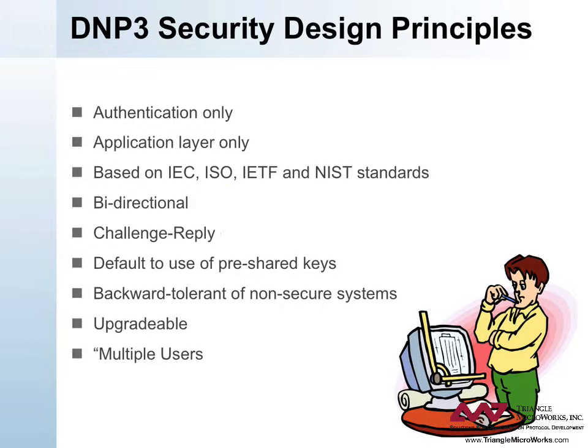DNP3 Secure Authentication was designed with the following principles in mind. Authentication Only: it addresses authentication only, not encryption or other security measures, as discussed already. It does not rule out the possibility of such measures being added to DNP3 later, or through the use of external measures such as a bump-in-the-wire link encryptor or TLS when used over an IP network.